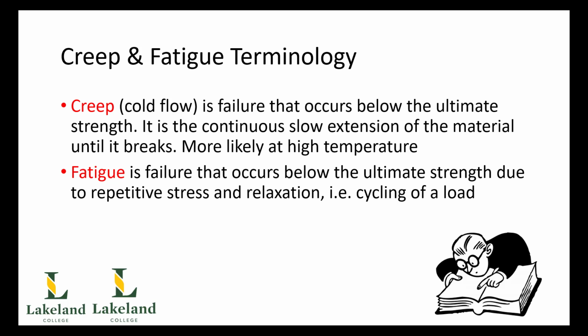Now, there's nothing really that we can do about creep. It's going to happen. However, creep is made worse with the increase in temperature. So if you think about our applications for boiler tubes and fire tubes, for example, these are steels that are going to be placed under a great deal of stress, pressure and temperature. So with the addition of molybdenum, we can reduce the overall effects of creep. Can't stop it, but we can restrict it.